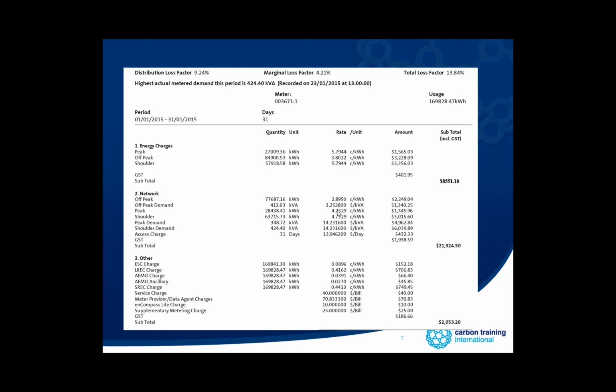The other thing they do is charge you what's called a demand charge on top of that. This represents the peak energy demand you've put on the network during that, in this case, 31-day period. This is a monthly bill, for 31 days, and you can see this kVA figure - the peak during the month in the shoulder was 424 kVA, and for each of those they charged $14.23, and off-peak was 412, charged at $3.25 each.